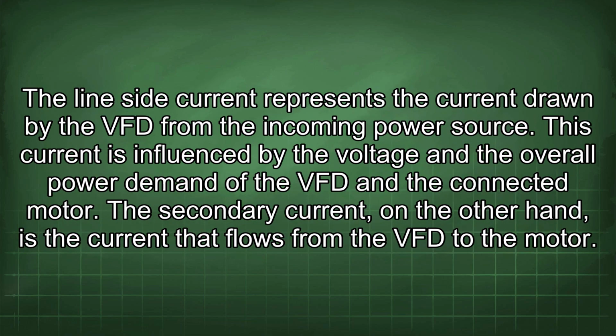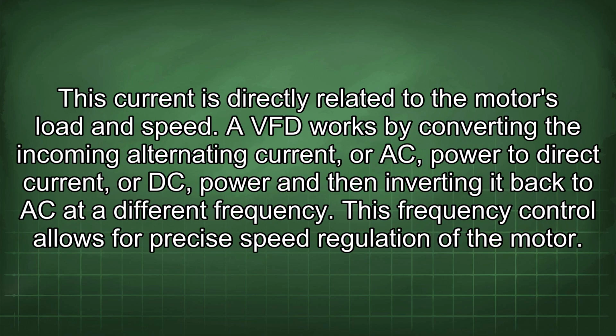The line side current represents the current drawn by the VFD from the incoming power source. This current is influenced by the voltage and the overall power demand of the VFD and the connected motor. The secondary current, on the other hand, is the current that flows from the VFD to the motor. This current is directly related to the motor's load and speed.